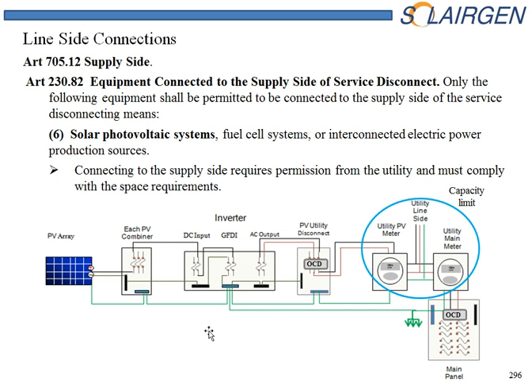Here we see a line diagram representing a typical residential installation. In this case, we have two meters. This is the line side of the utility, and this often requires a rebuilding of the service. Occasionally, you'll find a service that has capacity within the equipment to actually tap in on the line side. You'll have to look at the equipment and see if it's rated for it. If it is the utility's equipment, you'll have to get permission from them to make the tap. And if they say no, then you'll have to rebuild the service. That covers line side connections — utility scale is another matter and not covered here, but the rules basically follow the same.